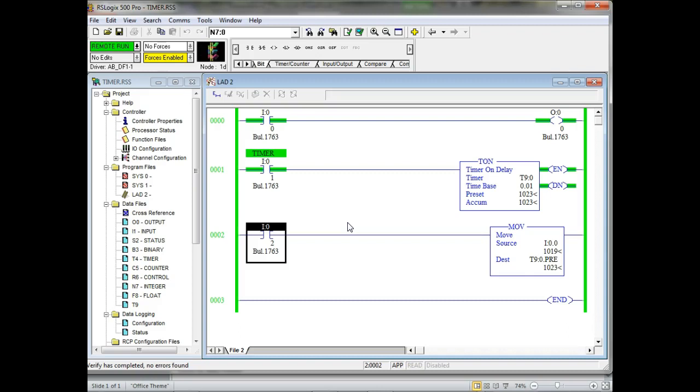These move instructions are very popular, but these move instructions, this is the source. So what could the source be? Well, the source could be the results of a math operation. The results could be the source of a logic operation. It could be the source of an input port, right? Understand that? I can bring that in. And then I can move it into a preset register. I can move it into the accumulator. I can move it into my counter, right? The preset on my counter. And in that way, we actually get a true variable where I can do it on the fly, right?